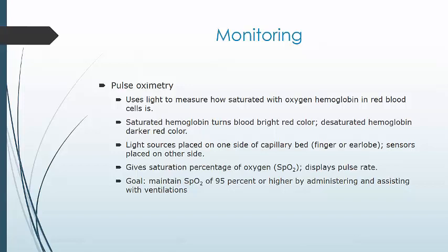What we're doing here is the light source of this pulse oximeter is placed on one side of the capillary bed, and sensors are placed on the other, whether it's a finger, an earlobe, a toe, whatever.